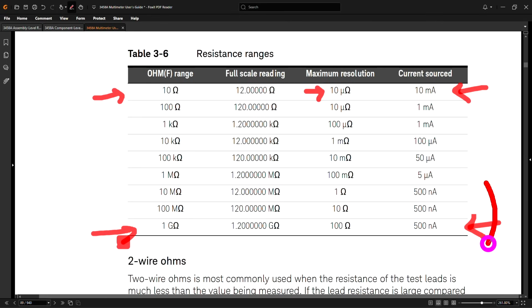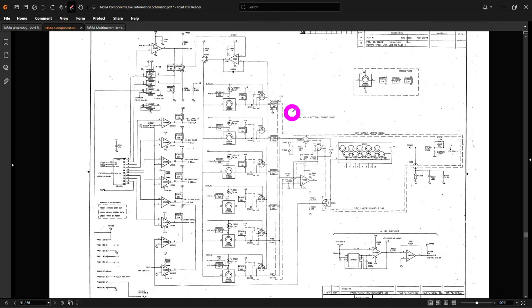So if you look here at the bottom, for the 10 meg, 100 meg, and 1 gigaohm range, it uses 500 nanoamps, so it keeps that constant, and it increases it as you go higher and higher. So we should be able to take a look at this and measure that. The reason I'm focusing on this part first is because that auto calibration routine must go through all of these ranges and compare the measurements via some internal known states so that it knows that it is actually working and it can zero and take care of all the various offsets that it may have internally. So this could be a problem, and that overload condition could indicate that something's gone wrong and it's overloading the ADC as a result of it. So we should really go and find where the schematic is that does this in the circuit. And among the many, many pages of schematic, I have found the area responsible for this ranging of the ohms measurement. And I know we're looking at it from a very high level here, but I will zoom in a second.